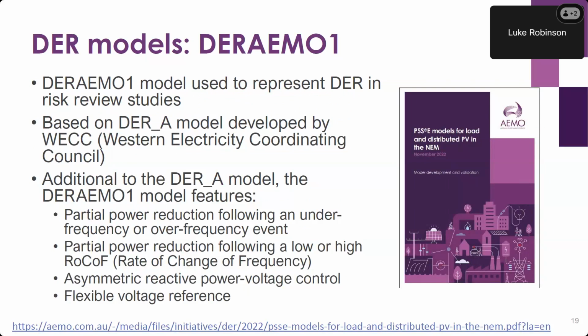So in addition to the composite load model, we've also added in the DER models. With these we can add in distributed photovoltaics at each bus individually. The amount of DPV inserted can be varied to match the historical dispatch for a certain date, or we can specify a percentage of online DPV.